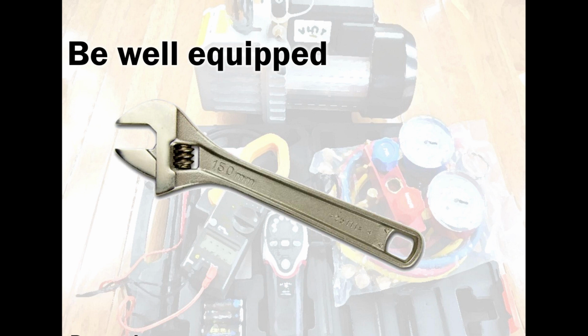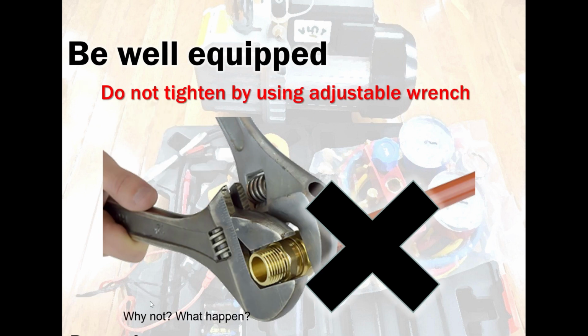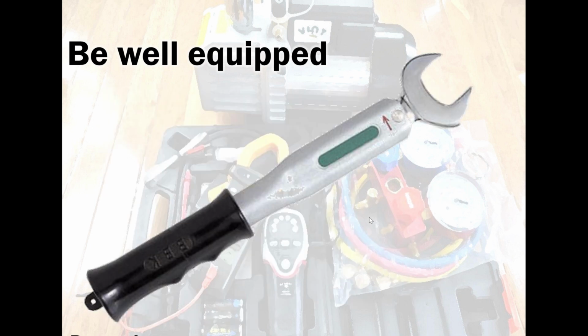Another problem we have is these wrenches. Most of my guys don't use torque wrenches. They say, I go by my feeling. I go by my experience. Don't use these adjustable wrenches all the way. You can use one for a startup, to start tightening, and when you get to a spot, please use this guy. All our tightening specs are mentioned in our installation manuals. Newton-meters, foot-pounds, you name it.